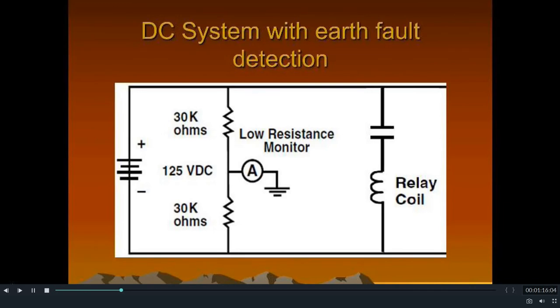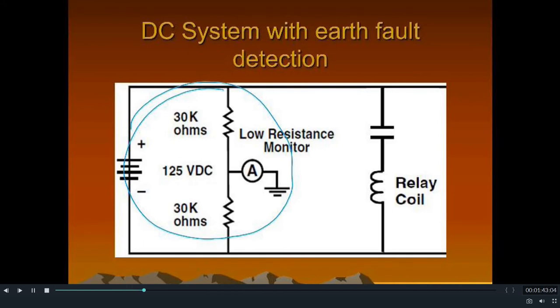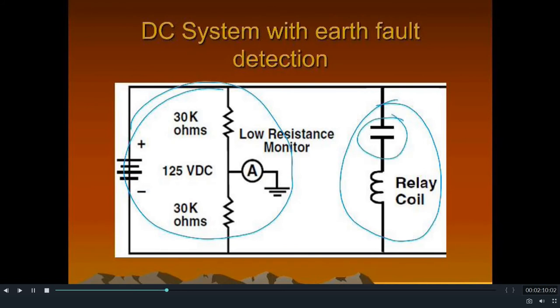Before we discuss DC earth fault in the system, let us understand how the DC system works. The DC DB of a substation consists of a battery bank which is connected to a high resistance that is also divided in between and connected to earth to get the virtual zero potential. This is the DC DB in a substation. On the right hand side of the circuit, the load is connected to the DC DB or the battery. The load consists of the relay, the circuit breaker, or any other coils. The battery DC positive and negative are separated from each other by NO contacts, which are provided over the coils as logic.